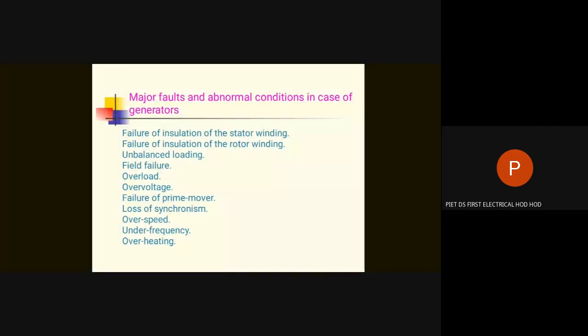Therefore, not only tripping of the breaker, but you have to trip the excitation system, you have to disconnect the excitation system, you have to trip the turbine, that means the turbine has to be stopped. One has to trip the boiler, one has to trip all auxiliary motors, particularly 6.6 kV motors like the primary air fan motor, boiler feed pump motor, FD fan motor, ID fan motor. That means all auxiliaries have to be stopped. The complete power station will come to a halt whenever there is a fault within the generator. Therefore, the whole protective system is going to be comparatively quite complicated.